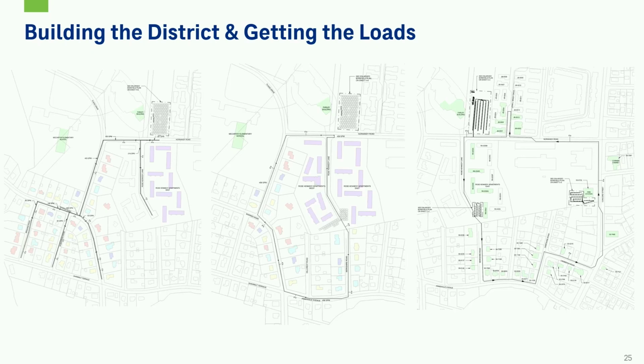So then we began to build our district system, and on the far left, you can see that we started out with a 2-pipe system. We had located the community college as that anchor customer, and we were putting one big bore field up in their parking lot, and then spidering out and getting some of those residential buildings to the left, picking up the elementary school, and then picking up those apartments. But then due to expandability in the future and some construction costs, we moved to a 1-pipe system and located a recharge bore field in the apartment buildings, and we're connecting some of the same residential customers, but starting to shift over a little bit.